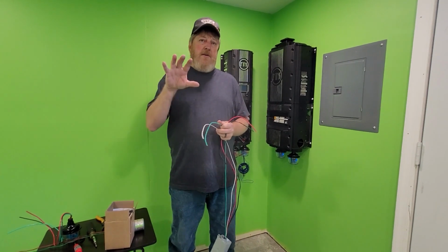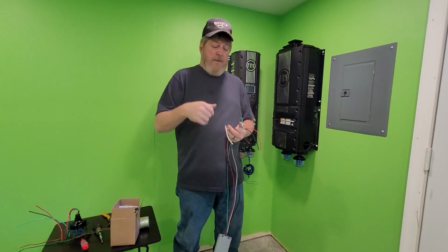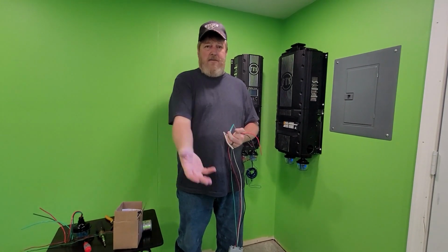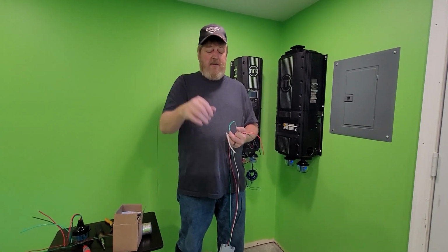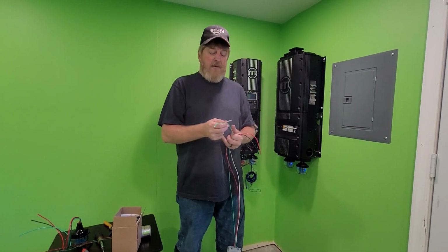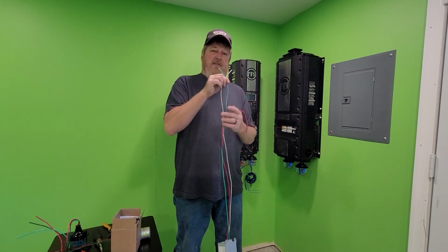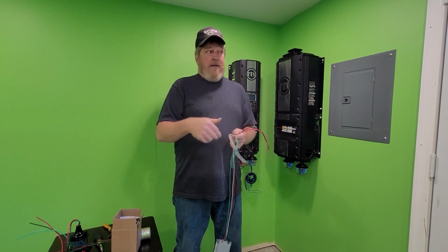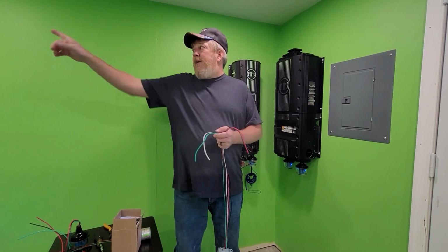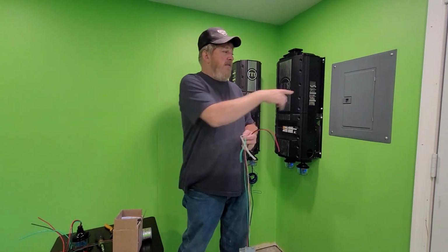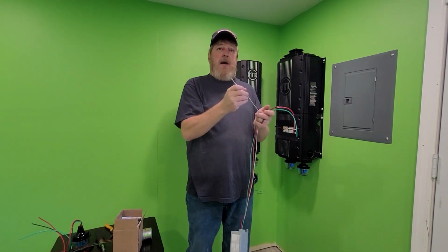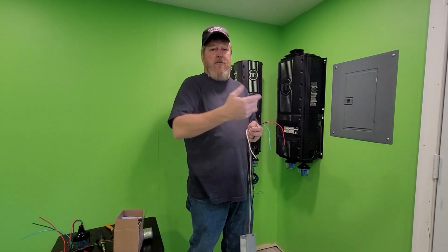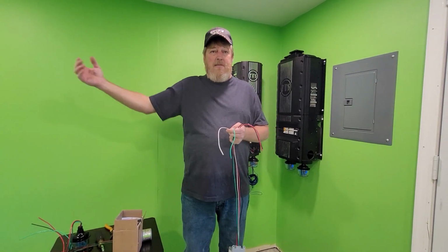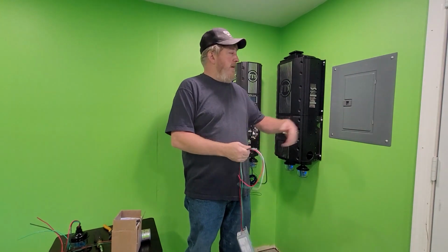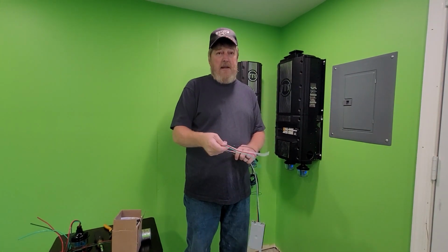Typically it's done in the meter socket or the main disconnect of the building. Like if your main disconnect is in your basement breaker panel and the meter socket's outside, the bond will be in that main disconnect. So at that disconnect, these are exactly at the same potential. But now out here, 50 feet away, if lightning strikes right out back here, this neutral could actually come hot, because that 50 feet of wire has quite a bit of resistance when you're talking thousands of volts in a lightning strike.